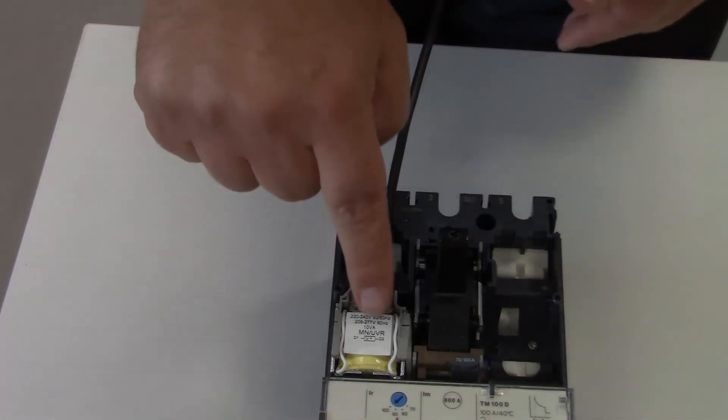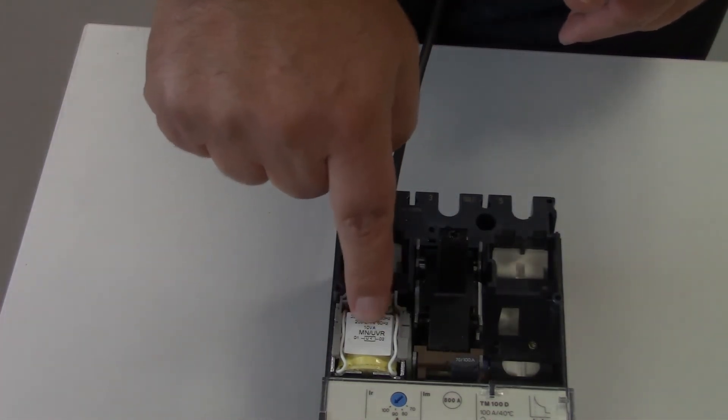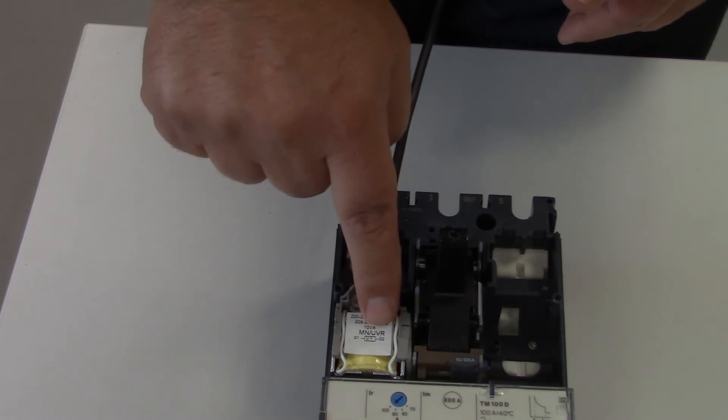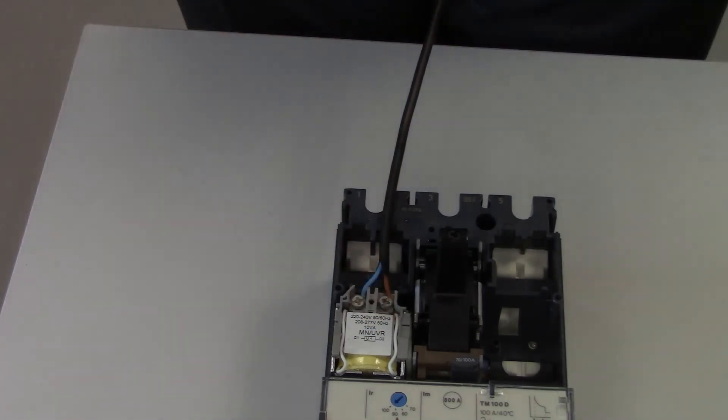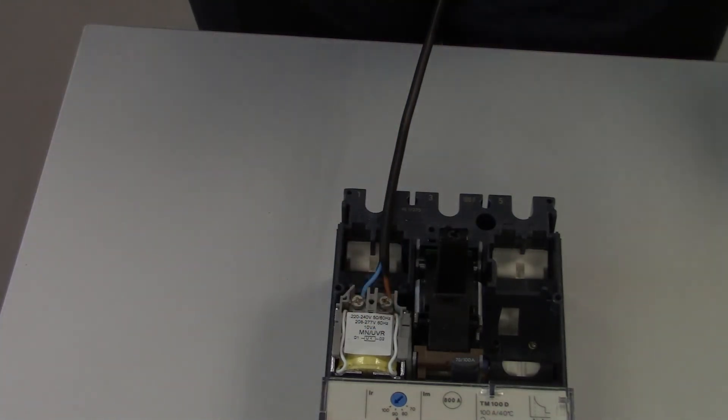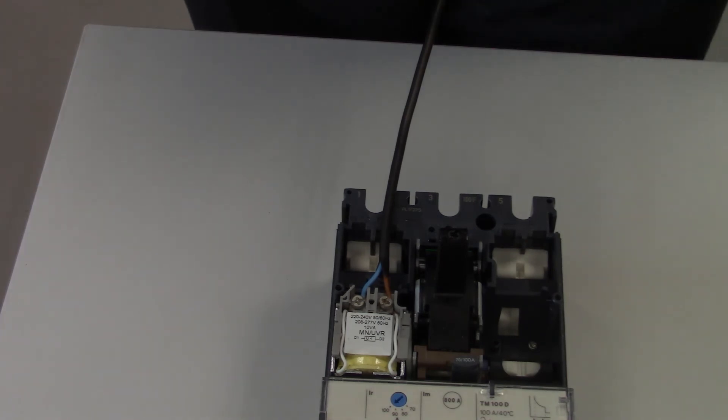in this case an undervoltage, an MN UVR. You could have a shunt, MX shunt, there as well, but there it is clear as day. That's how you know if you've got one of these devices or not.